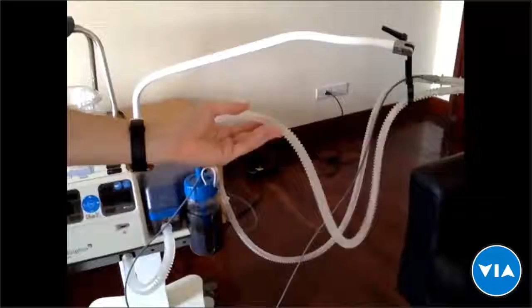So the difference made here for this device versus the developed world device is, first of all, obviously the upfront price, but more importantly, the running expenses of the device. The big difference is made by the reusable patient circuit. We chose the silicone grade that is possible to withstand high pressure and high temperature disinfection. So autoclave is possible with this patient circuit.